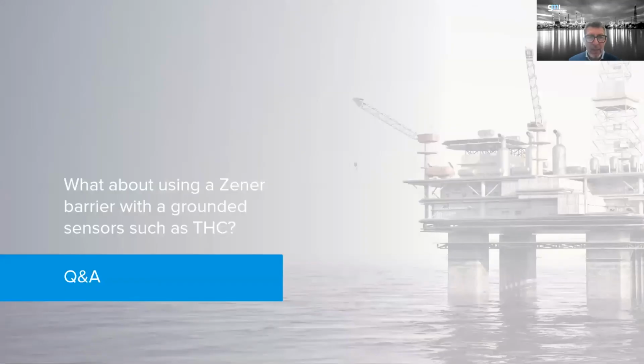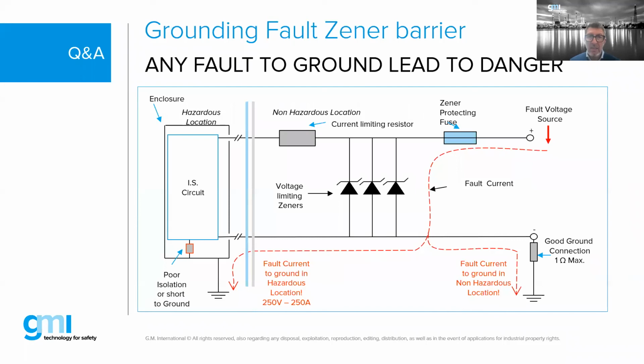Let me see. What about using Zener barriers with the grounded sensor? We said this earlier, I believe we cannot do it. Right, Bob? Yeah, no. Correct. We cannot do it because if we use a grounded sensor, then we have two paths for that fault current to go, either in the IS ground or the field sensor grounding.